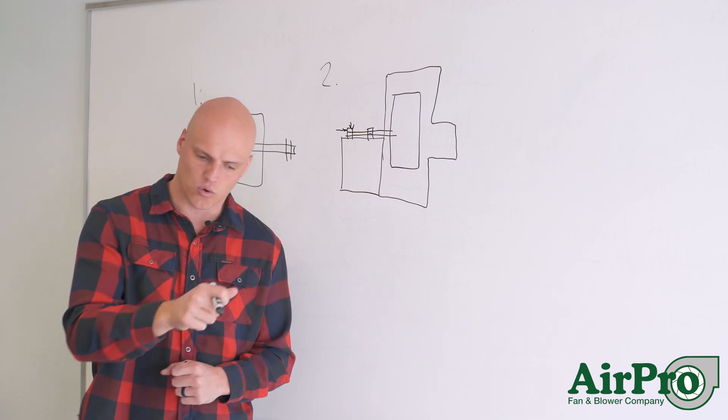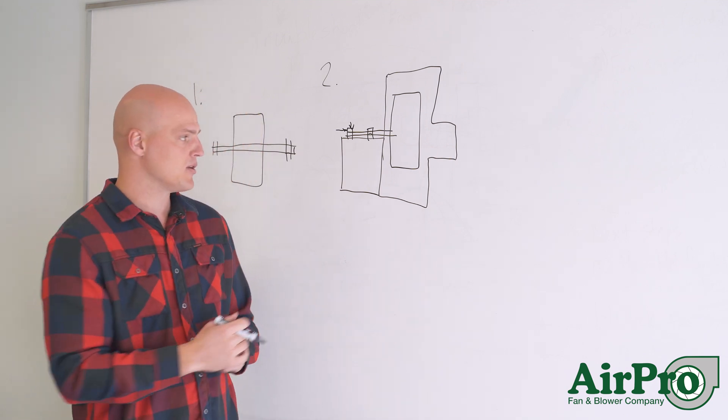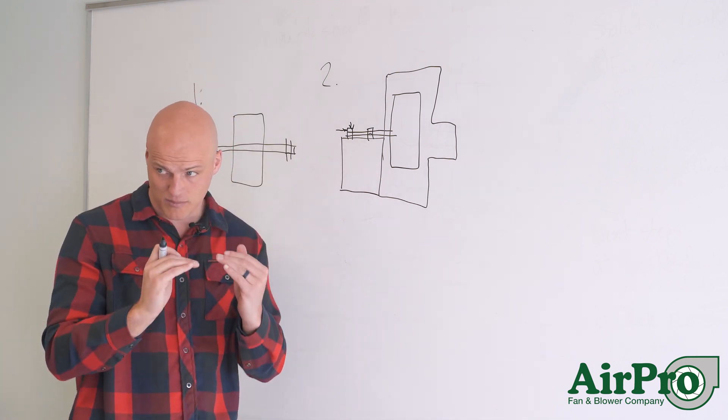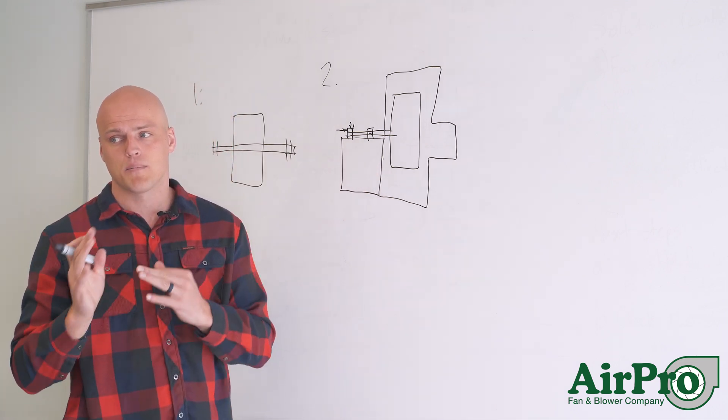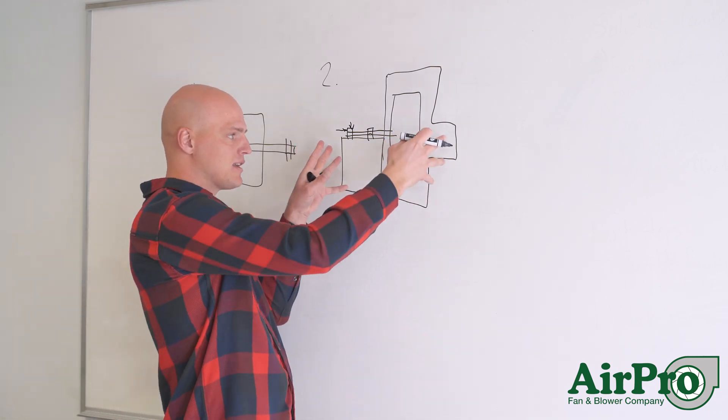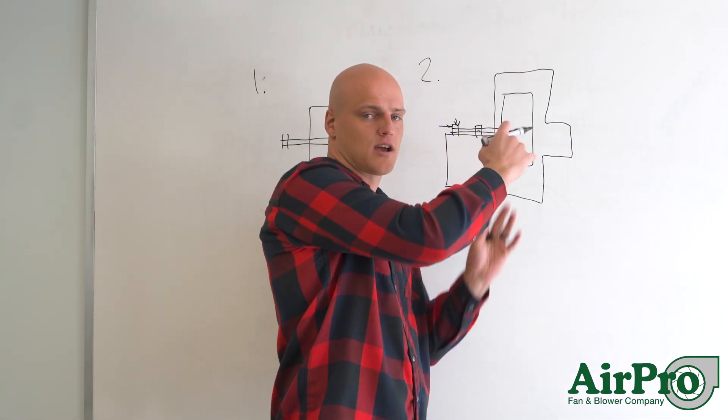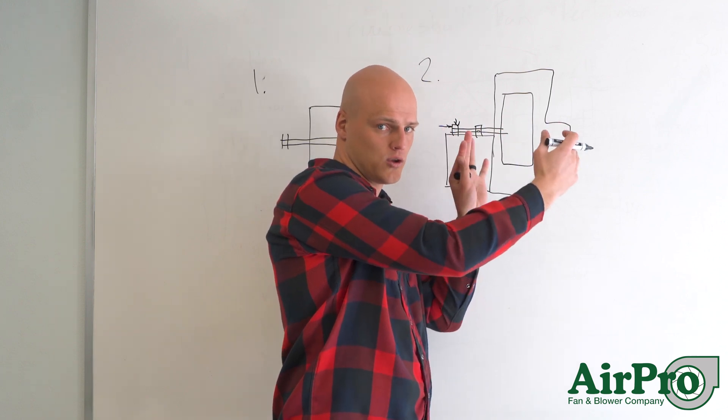You grind a little weight off, you weld a little weight on, maybe you'll have to add stiffness in your system to get your fan down to the balance levels it needs to be at. But that's why we consider this to be a balanced fan when you're within the vibration limits of the complete assembled unit.